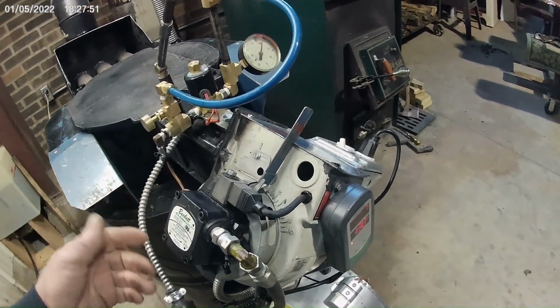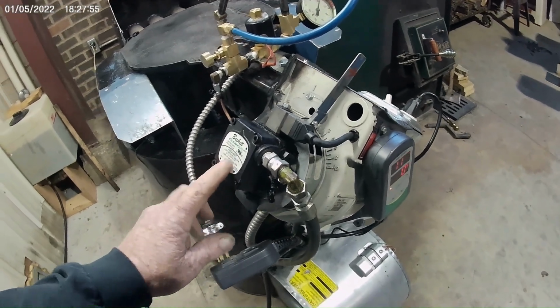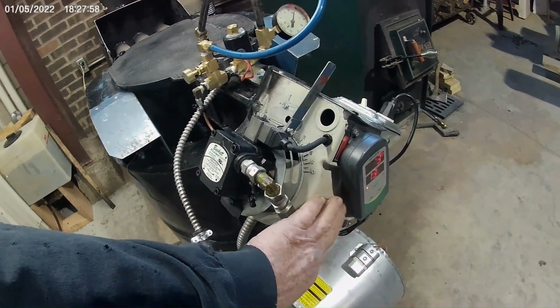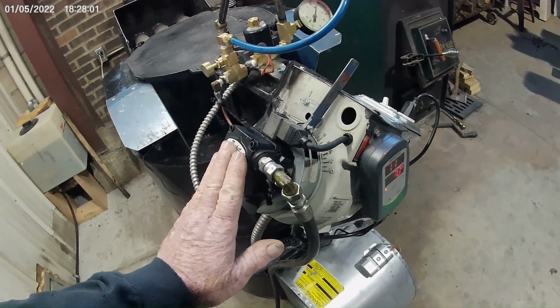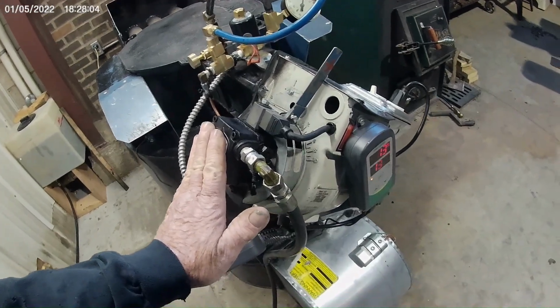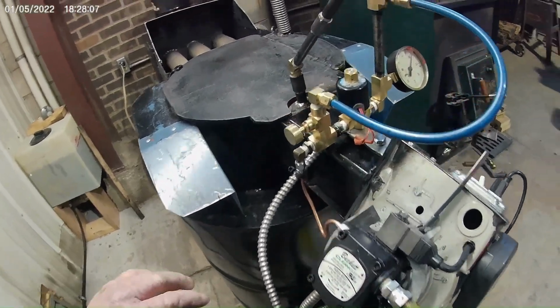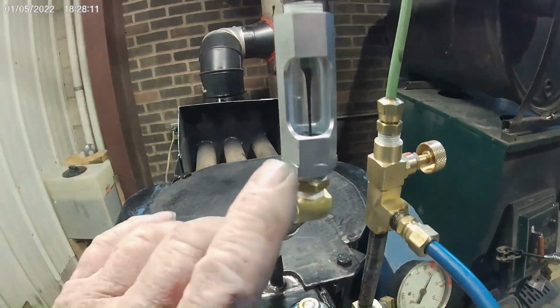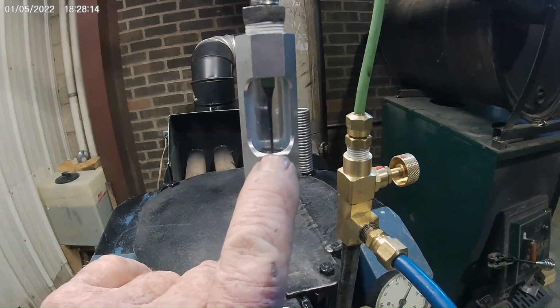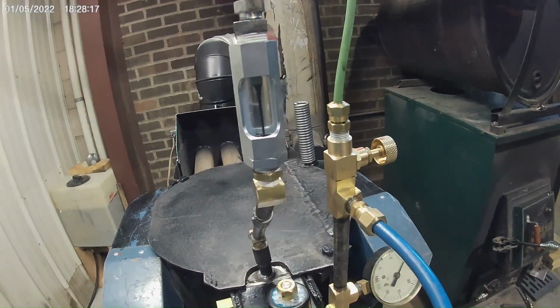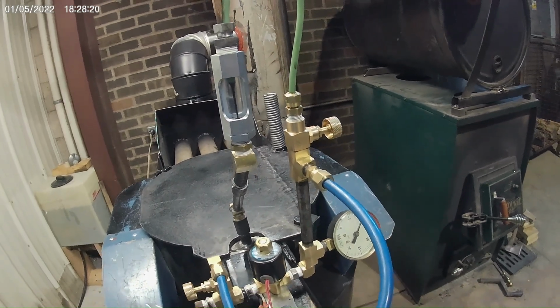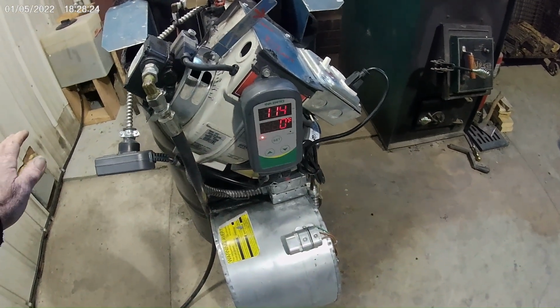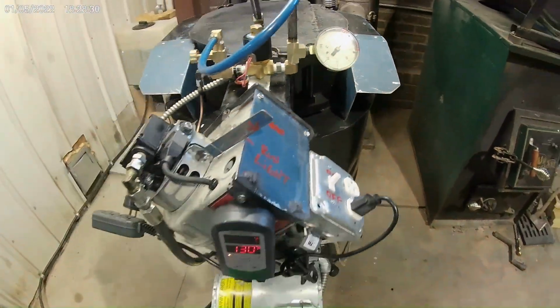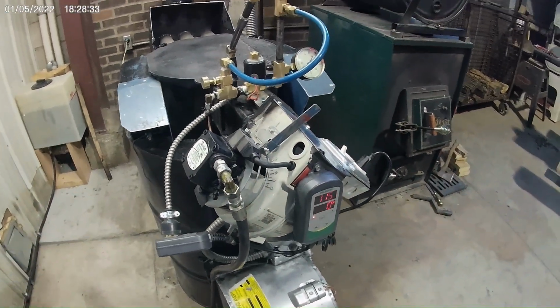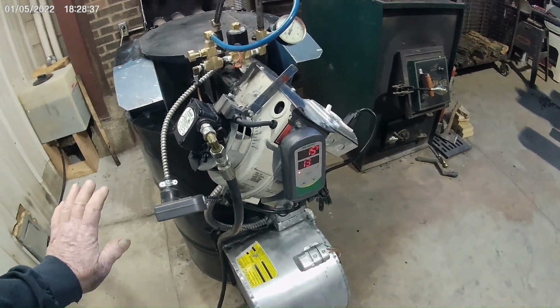You could put an oil pressure regulator on it if you wanted to, but you really don't want this pump working very hard. You don't want this pump to take all the horsepower away from your fan motor and everything, and the higher your pressure, the more horsepower you're going to steal out of your motor. So you can see here the stream of oil that we're running, about a 1/16 of an inch at the bottom. This stove right now is burning a gallon an hour, and it's holding steady at 114. So I'm going to turn it up to medium, speed the fan up a little bit, and if it holds that, then we'll speed it up again and put it on high.